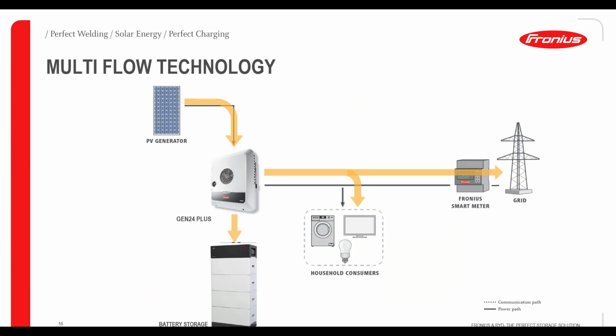The technology we've been using in our hybrid inverters is multi-flow technology, which means you have a battery in the system while supplying the household. You are charging the battery at the same time as taking surplus energy from it to supply the household, to cover more loads when needed. At the same time, you can even charge the battery from the AC side - you just need to activate that function in the web interface of the inverter, defining that you also want to charge the battery from the grid. All this can happen at the same time, which is called multi-flow technology, something we've used even in our previous hybrid inverters.